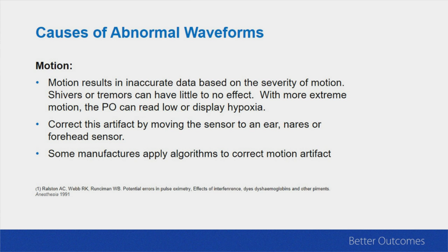Now, other manufacturers, there's at least one that I'm aware of, actually take this photoplethysmography technique that we're talking about, and then they apply algorithms to that data to correct for motion artifact. So they're taking a troublesome situation, whether it be a patient thrashing in bed or a patient you're trying to monitor on a pulse ox as you walk down the hall, and they're trying to correct that so you get a true number. So this is the enhanced versions of a pulse ox.